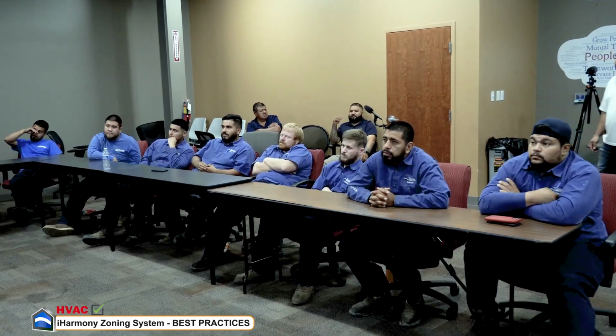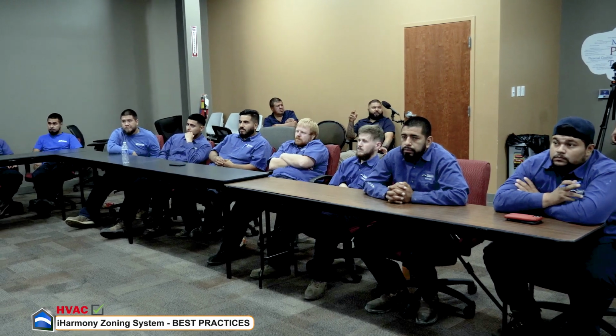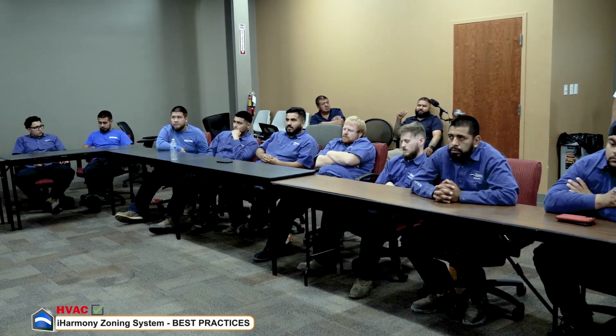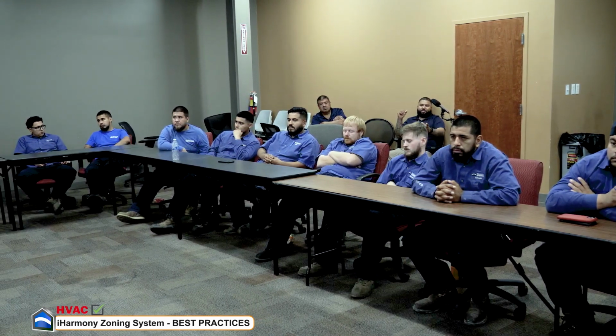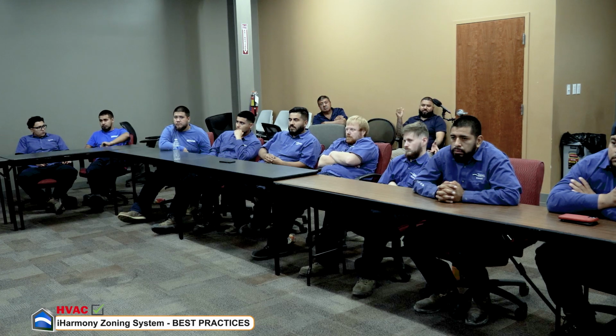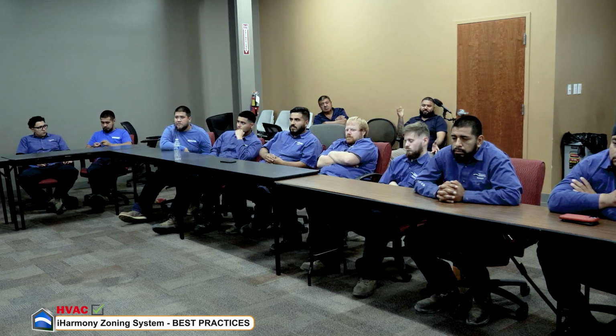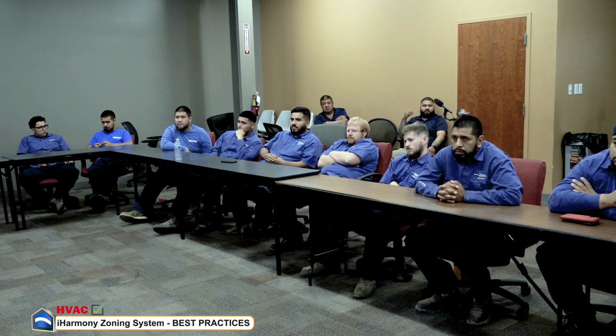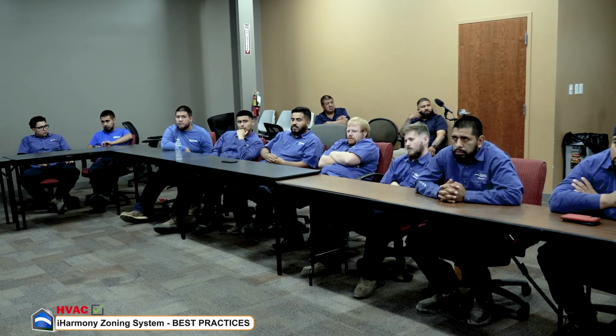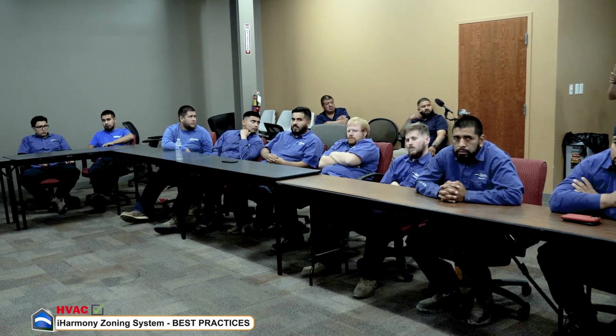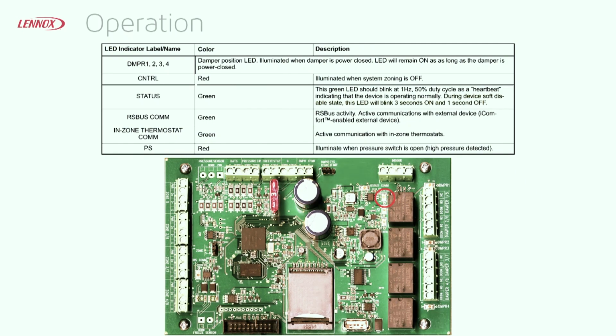I've got a question about fresh airs. I know Honeywell has two-wire fresh airs. They go to the A1, is it A1, A2? But then when you have fresh airs that are 4-wire with that module, would it work with our Harmony setup to do fresh air? So the iHarmony won't, but the S30 will. That's a good question. That's going to tie into the S30.